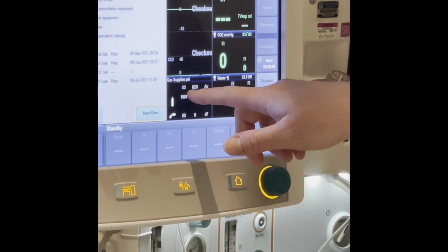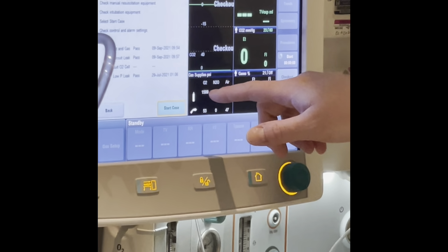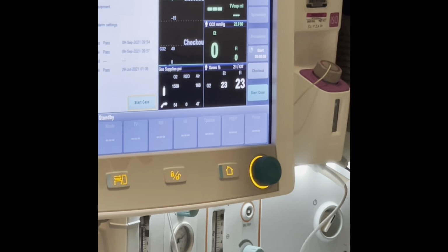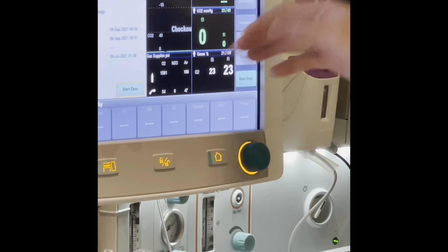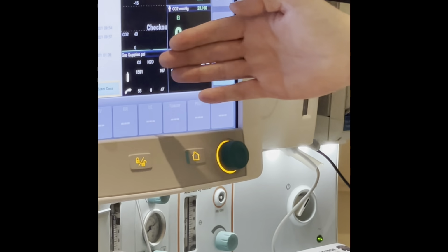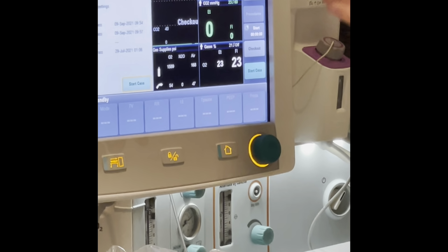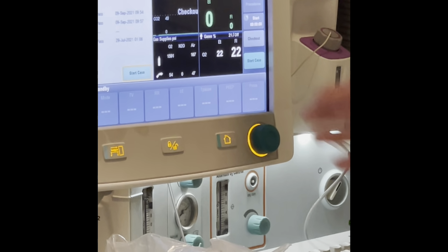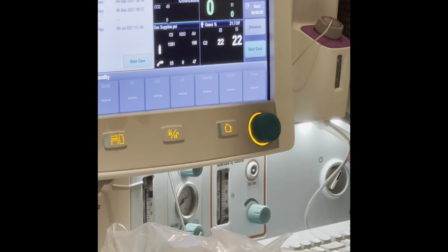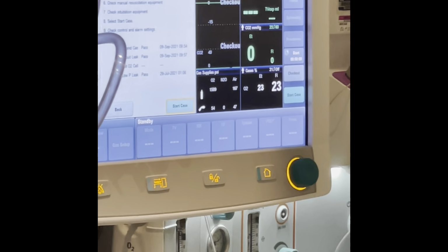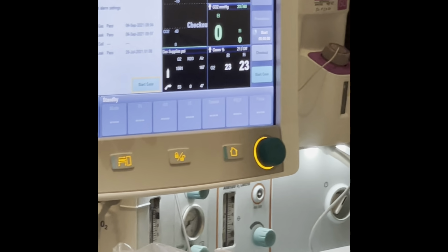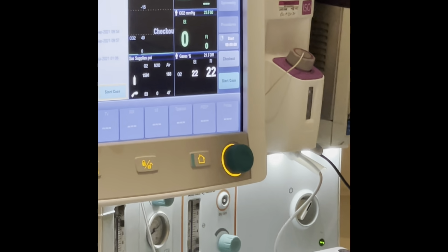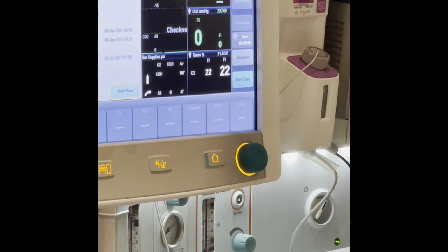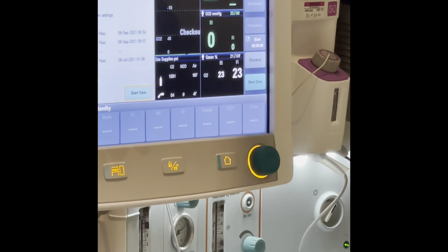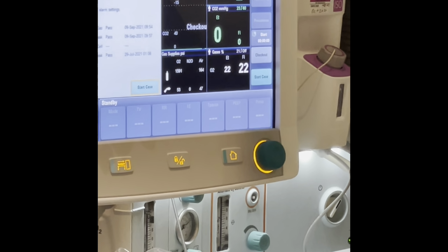This is measuring the pressure inside the tank, and it's only accurate if you open it. So right now, it should be closed, and so it might just be reading what was done before, and that will slowly downgrade. So don't trust this number, do your own check. Does anyone remember what the pressure should be in the cylinders, in the oxygen? 2,000. For oxygen. Yeah. And what about 1,900 for air? Yeah, it's about the same, like within 10 of the 2,000.